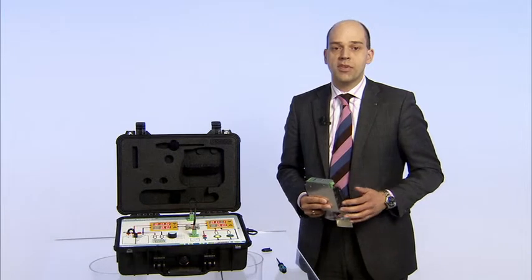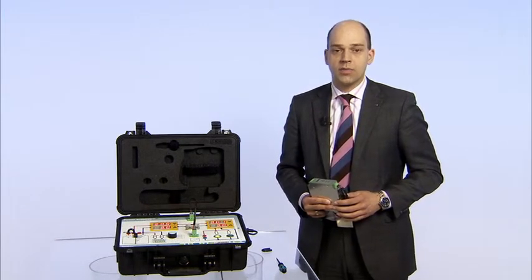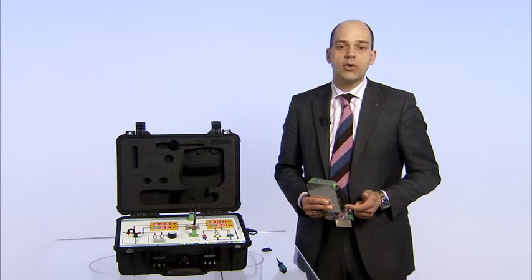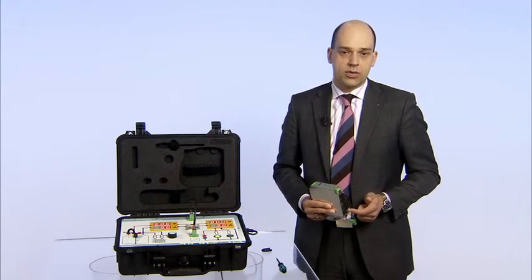Firstly, it stabilizes fluctuating voltage sources and compensates drops in voltage on long cables. Secondly, independent supply systems can be integrated thanks to safe electrical isolation. Thirdly, SFB technology ensures swift triggering of standard circuit breakers through dynamic power reserves with up to 6 times the nominal current for 12 milliseconds.